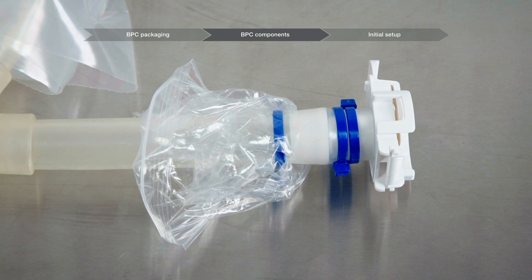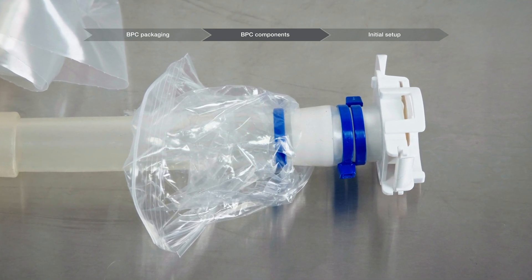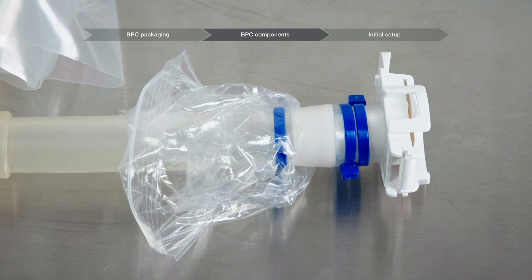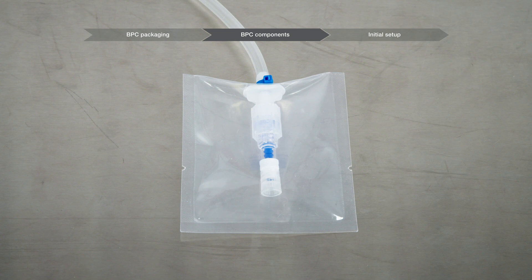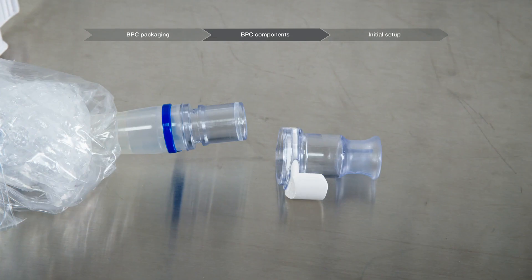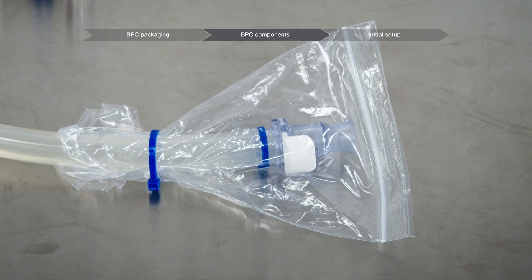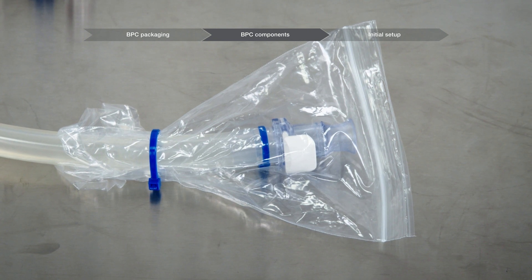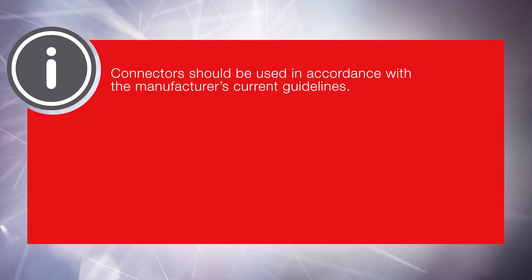Connectors allow a line set to connect to another BPC, tubing assembly, vessel, or other equipment. Various types of connectors exist, including aseptic, steam through, and small volume sampling. Depending on the BPC design, many connectors can have liquid-tight terminations such as caps and plugs. In other circumstances, only dust protection barriers are used in addition to poly bags. Connectors should be used in accordance with the manufacturer's current guidelines.